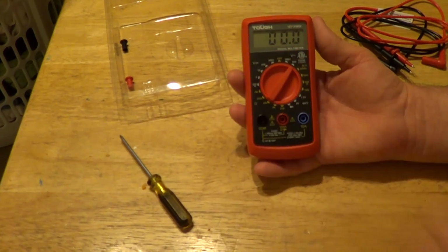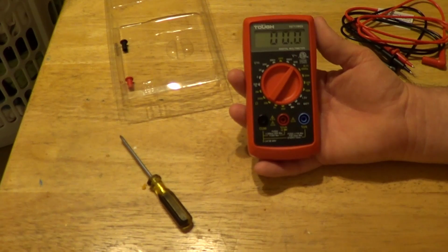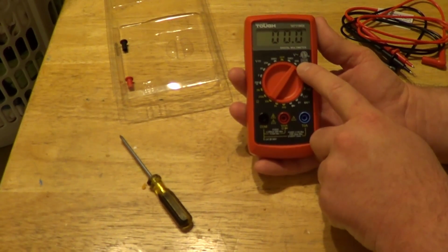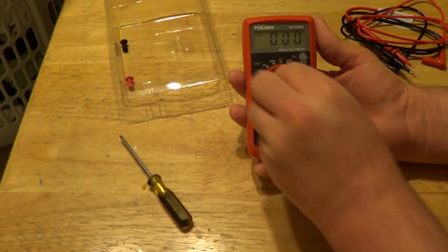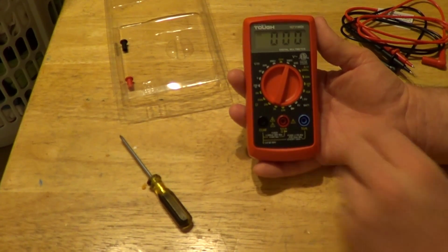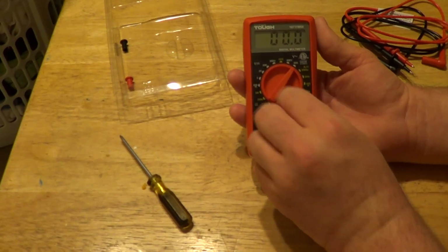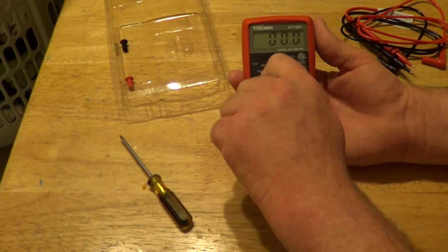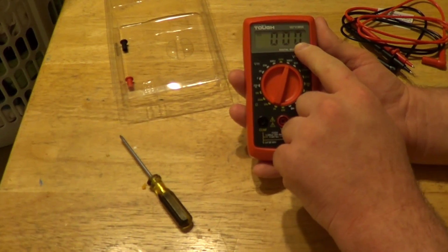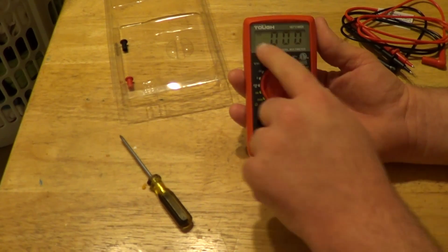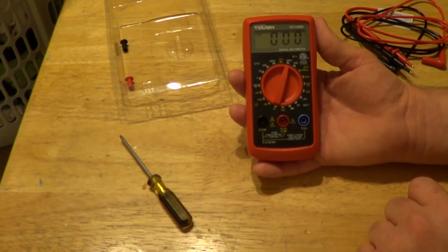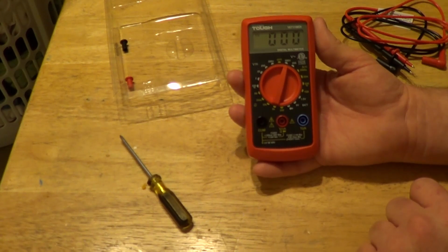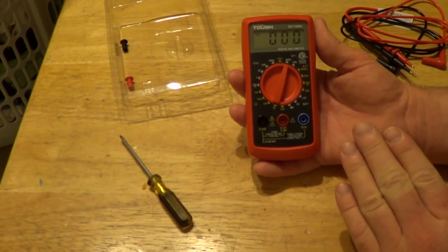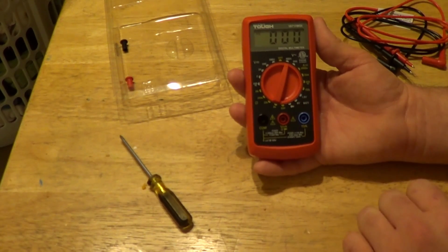Then we move to the final two testing ranges, both for AC voltage: a 200 volt setting and a 300 volt setting. When we switch from 200 to 300 volts, we lose a digit's worth of precision, and the HV indicator comes on again in the display. Certainly any voltage above about 30 volts AC or so should be treated with the utmost respect.